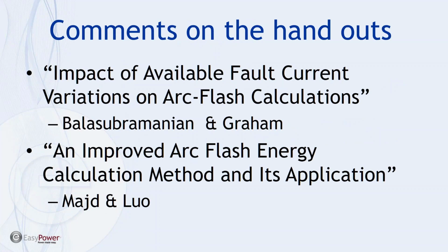I've included a couple of handouts which are available in the control box for this webinar. One is a paper produced by a couple of engineers from the Eaton Corporation entitled Impact of Available Fault Current Variations on Arc Flash Calculations. Very good reading, and it does have a direct bearing on the issues you run into when you have a very high motor content in a motor control center.